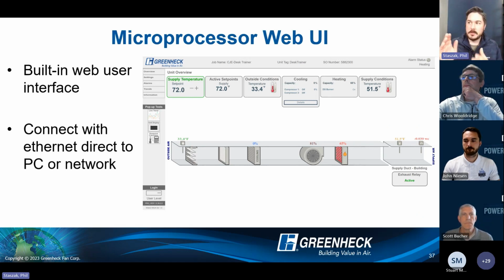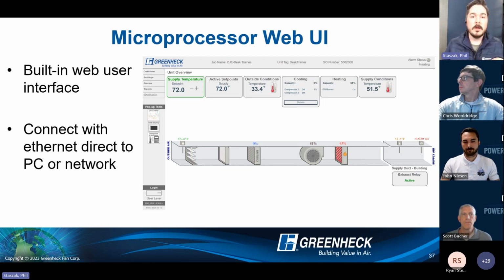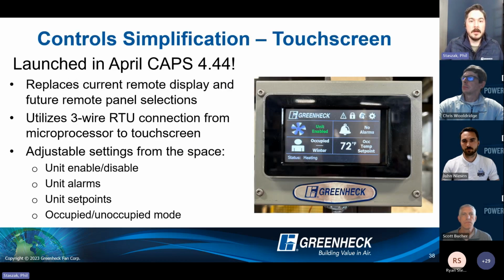Local network stuff. So you take your internet connection, Ethernet cable, land it on the controller in the unit. We will punt out the IP address for you to use on your local network, and this is what will come up and populate. Now, BMS, different conversation. We need to know, is it BACnet MSTP or BACnet IP, and we can give you a protocol to talk to a unit. There, if you want to control a unit from California and you want to control something in Maine, that's where BMS comes in. If you want local compatibility, that's where the web UI kind of comes into play.